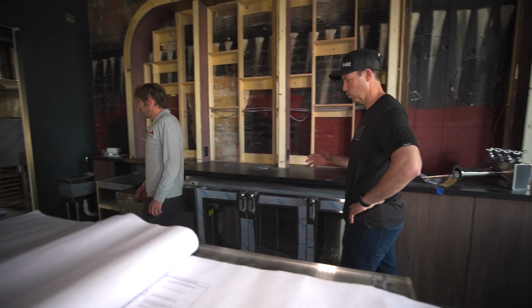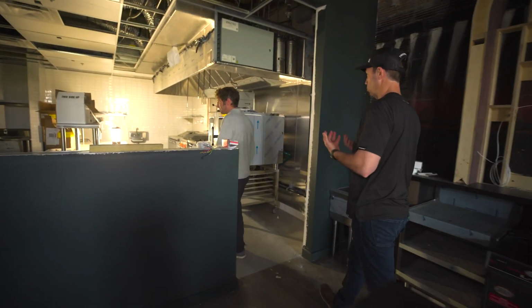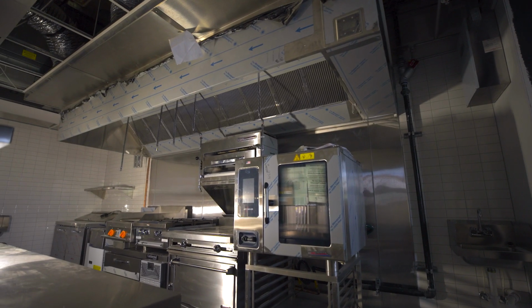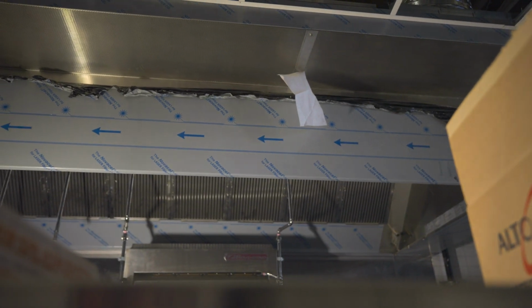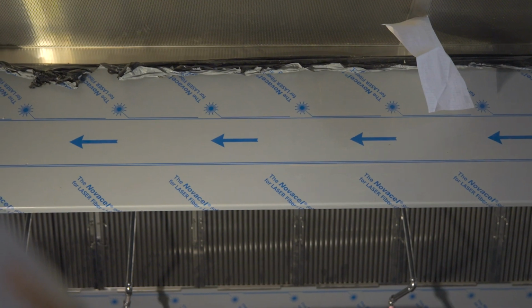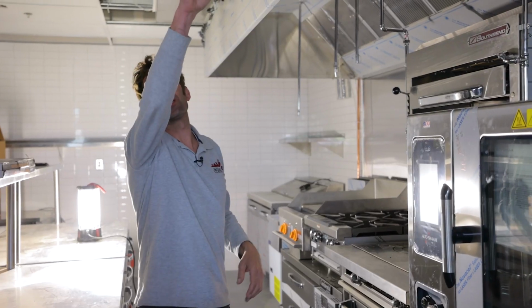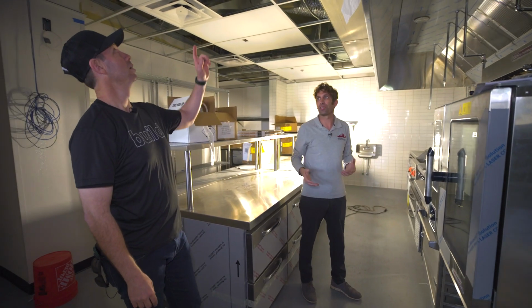You know, I've always wondered in commercial kitchens, for instance, I know that there's some requirement for makeup air. This hood looks ginormous. How do you get all that coordinated? And is this an off-the-shelf part, or is this custom built? It's custom built. So all of these, you are correct. This is an exhaust hood, just pulling air out, and then we have to make that air up with makeup air. So we're introducing air and we're exhausting it so that the pressure doesn't become super negative.